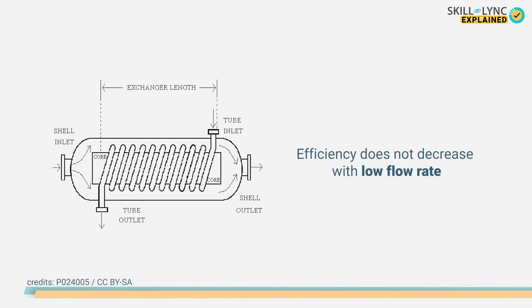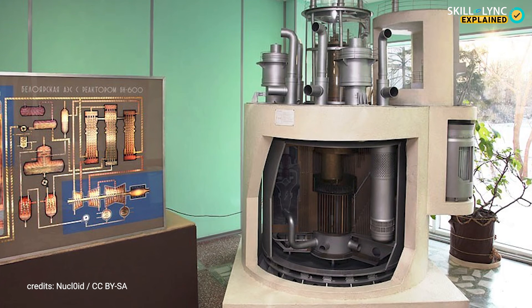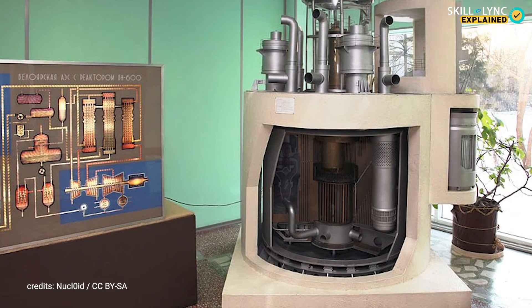Moreover, when the flow rate is low, the efficiency of shell and tube type heat exchangers is decreased, but this is not the case with helical coil heat exchangers. The cleaning of helical coil heat exchangers can be difficult as compared to straight shell and tube type, but at the same time, helical coil heat exchangers require cleaning less often. These exchangers are most widely used in liquid metal fast breeder reactors.